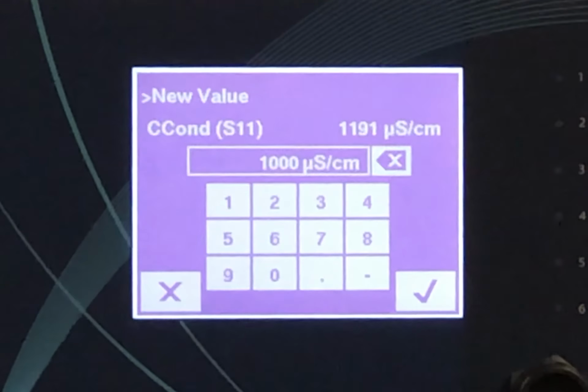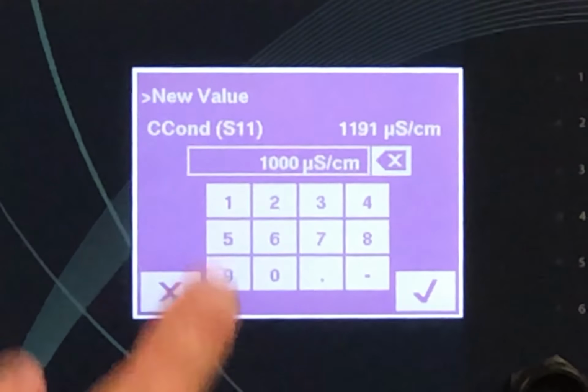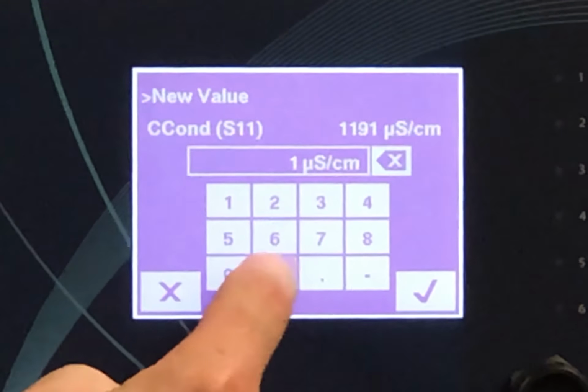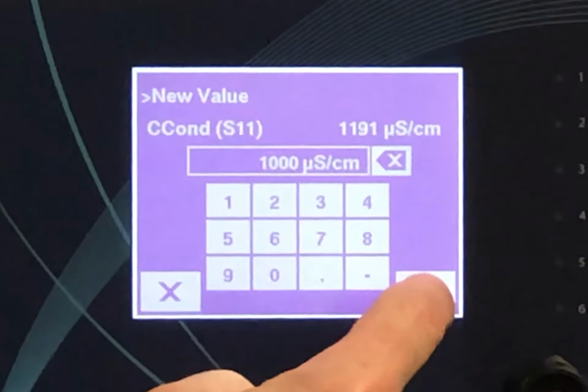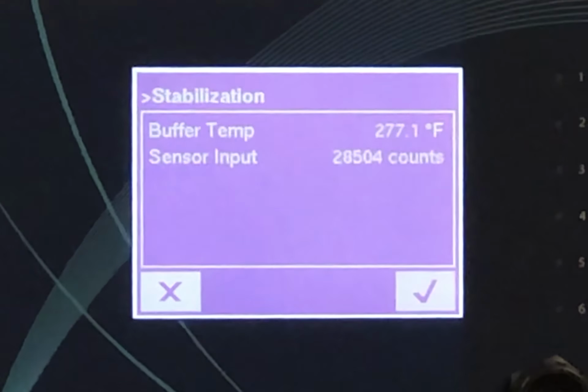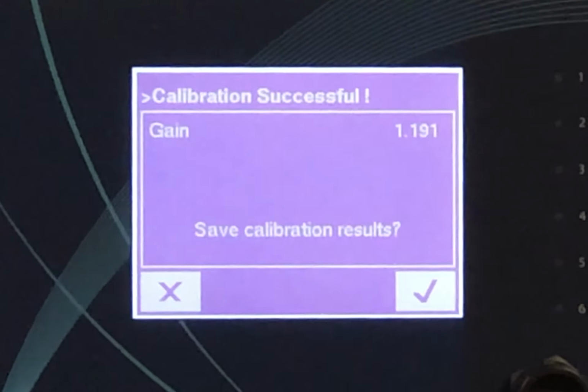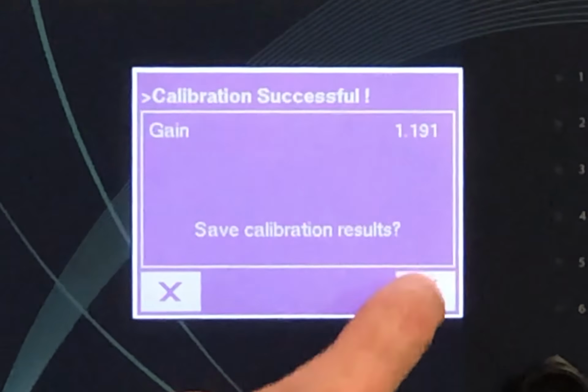Next, enter the test result you received from your handheld conductivity meter and hit the check mark. Wait for about 30 seconds and you'll see the screen show calibration successful. Hit the check mark and you're good to go.